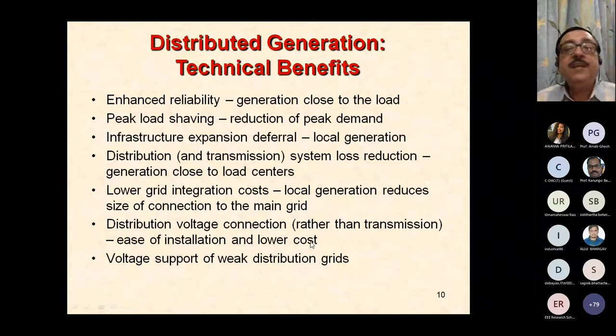There are definite distinct benefits of distributed generation. First is enhanced reliability. You have the generation close to the load. So as I said, if there is a problem in the transmission line or elsewhere, your local load need not get totally interrupted. It all depends on the capacity of your local network. You can have peak load shaving, that is reduction in peak demand by taking the power from the local network through DGs from solar. You have deferral of infrastructure expansion because you're going in for local generation. You don't have to expand the capacity of your transmission lines.